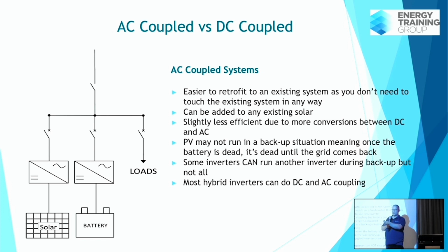A lot of backup inverters, when they're in backup mode, actually put out a sine wave at 52 hertz or 52.5 hertz. So as we know, all grid-tied inverters at 52.5 hertz are not going to connect, right? It's not going to start because it's not within the required grid values for our grid-tied inverter to actually start.